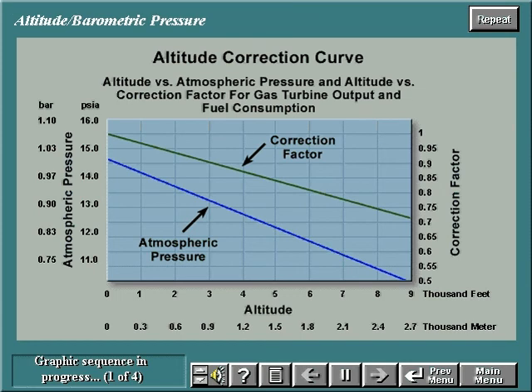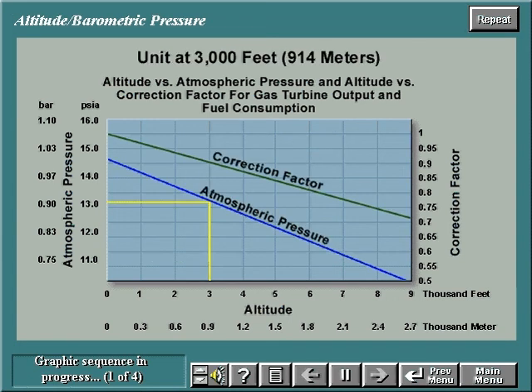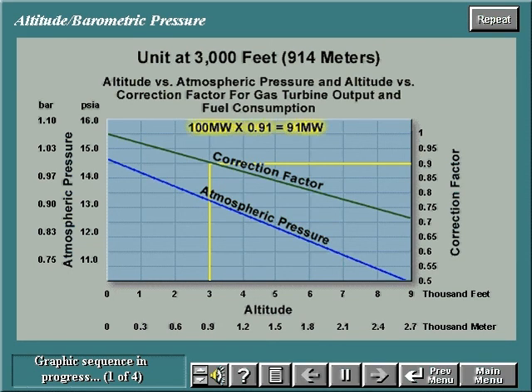This graph shows the effects of altitude and barometric pressure on gas turbine performance. A decrease in air density reduces mass flow and output proportionally. Heat rate is not affected. For example, a unit installed at an altitude of 3,000 feet would require an atmospheric pressure correction of approximately 13.2. The correction factor for the output and fuel consumption would be approximately 0.91. If a gas turbine with a nameplate rating of 100 megawatts is installed at this altitude, the expected output would be 100 times 0.91, equaling 91 megawatts.